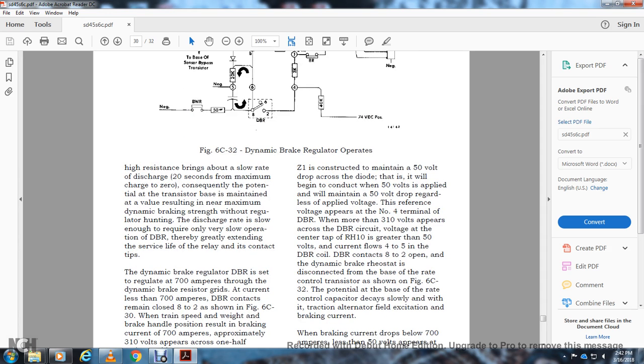The Zener constructed will maintain 50 volts across the diode, which will again conduct, maintaining a 50 volt drop regardless of the applied voltage. The reference voltage appearing at number 4 terminal of the dynamic braking regulator is more than 310 volts across the dynamic braking regulator. The voltage at the center tap of the rheostat is greater than 50 volts, so current flows through 4 and 5 of the dynamic braking regulator relay coil. The dynamic braking regulator contacts 8 and 2 open, opening the dynamic braking rheostat connection.